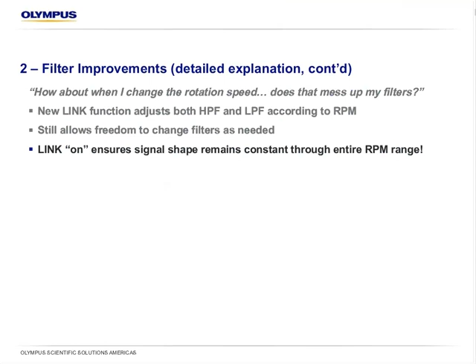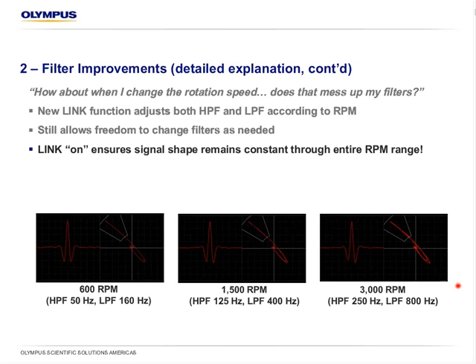Here are 3 examples. Let's say we calibrate at 600 RPM, very low speed, high pass 50 Hertz, low pass 160. Now we increase to 1500 RPM, and the link automatically adjusts those filters - there's basically no difference between the two because the filters are properly set in both cases by the link function. Even if we stretch to 3000 RPM, the high pass and low pass get adjusted and the signal remains the same. The only difference is that 3000 RPM might be noisier because there's more vibration at higher speeds, but that's pretty much it.